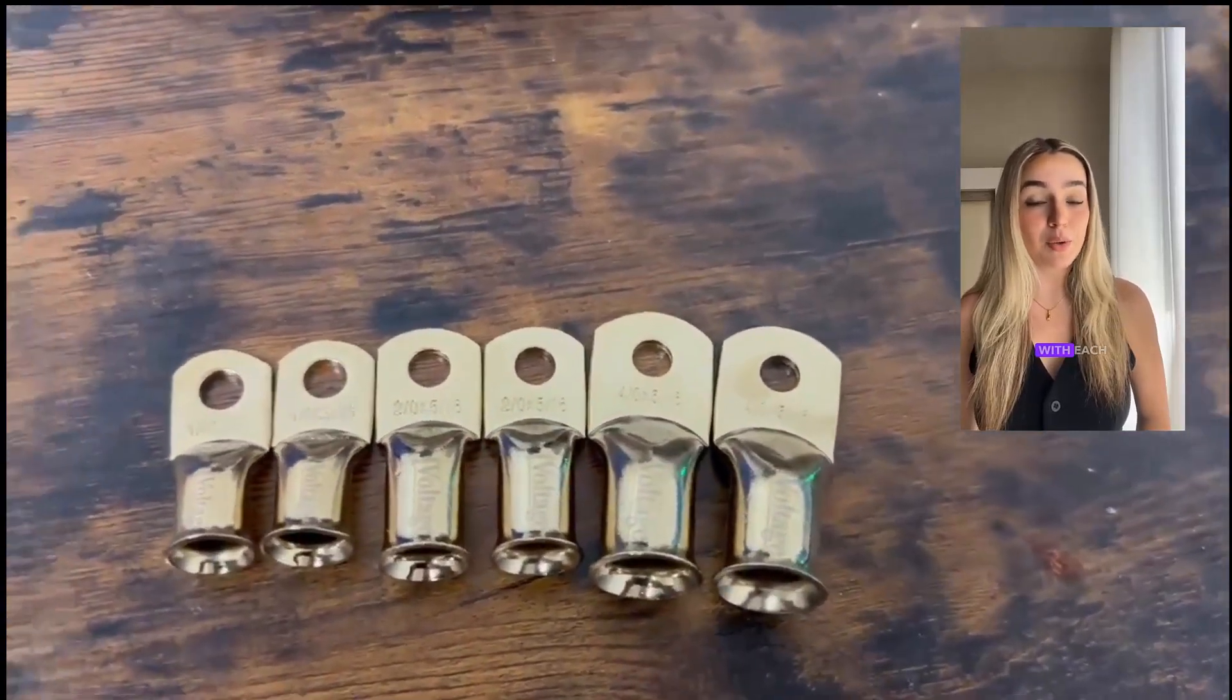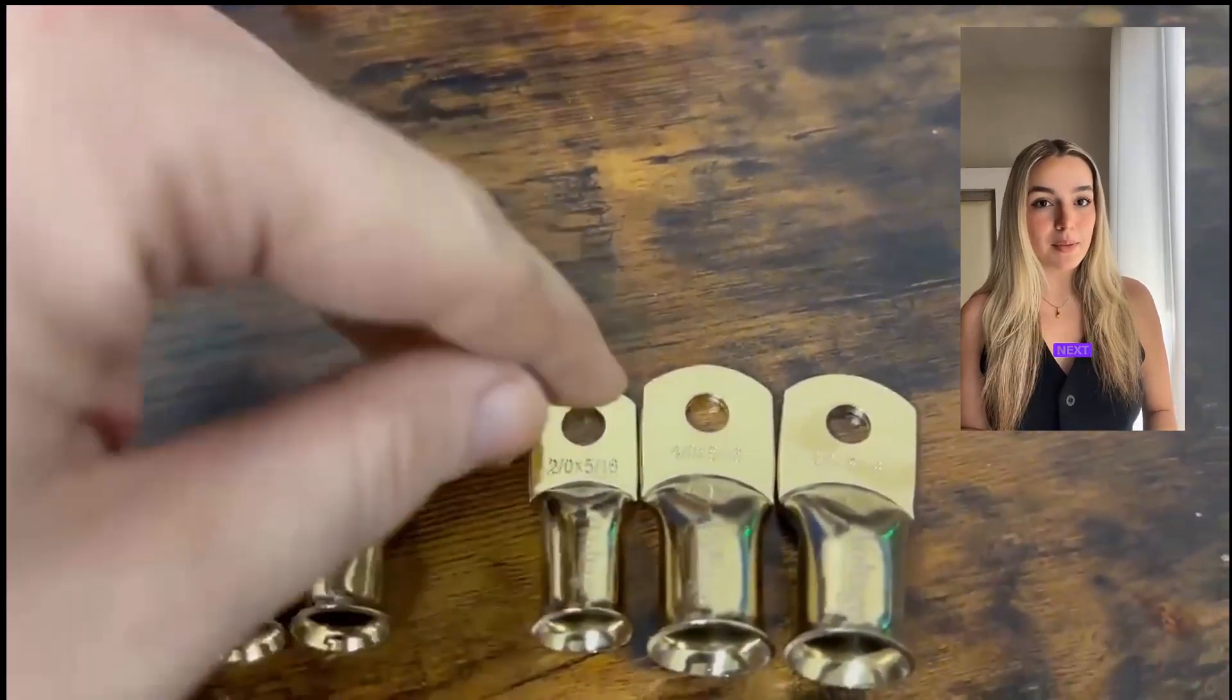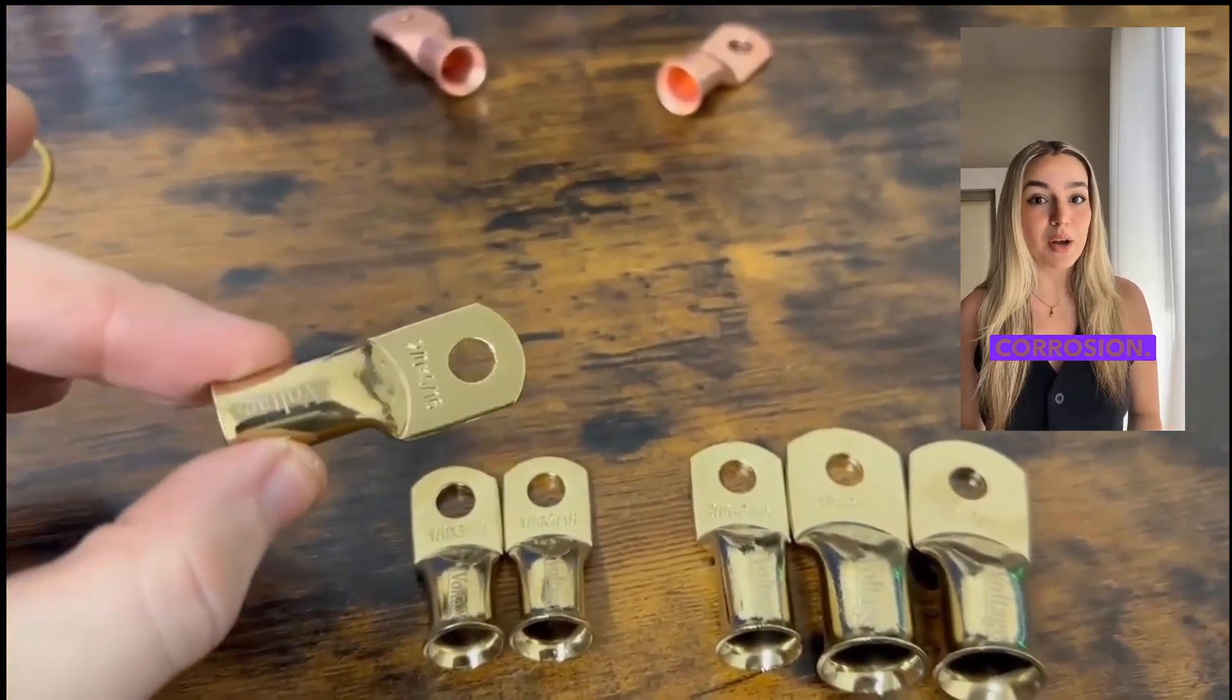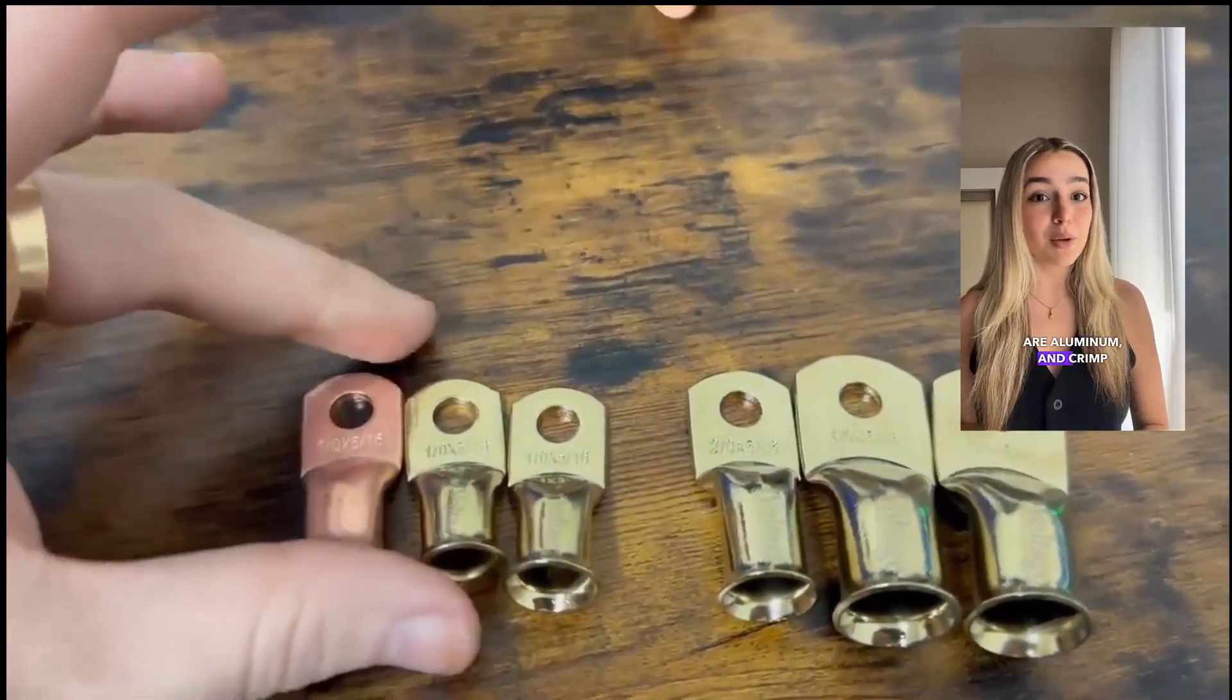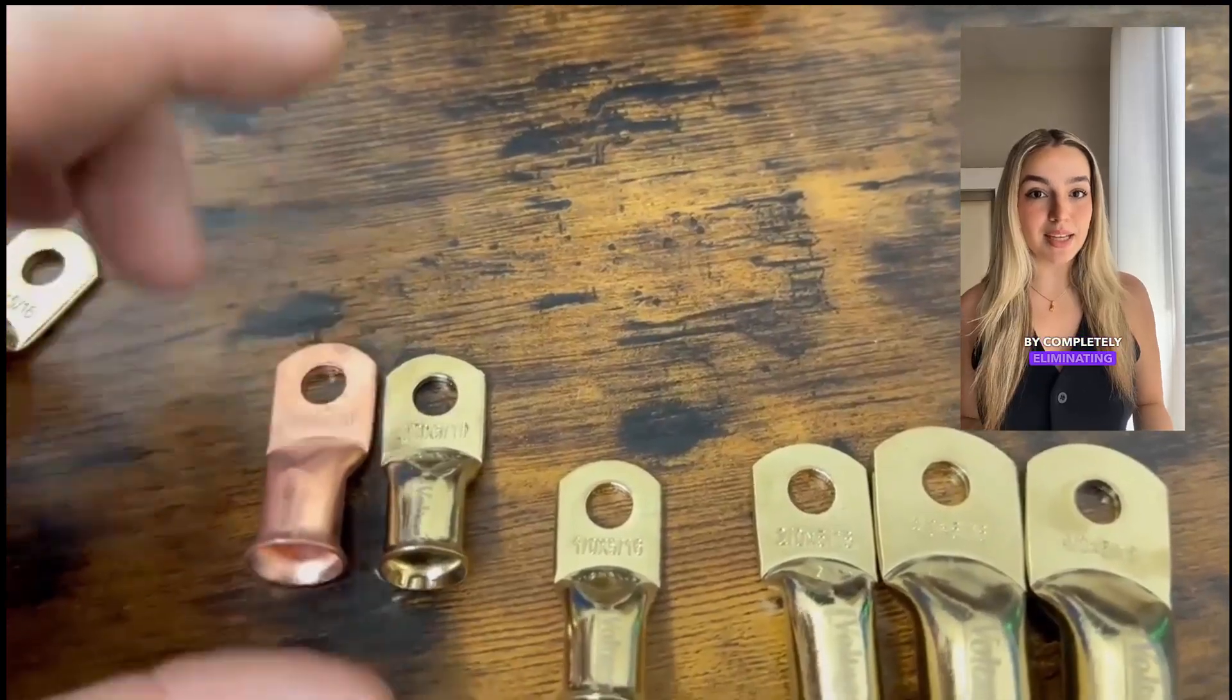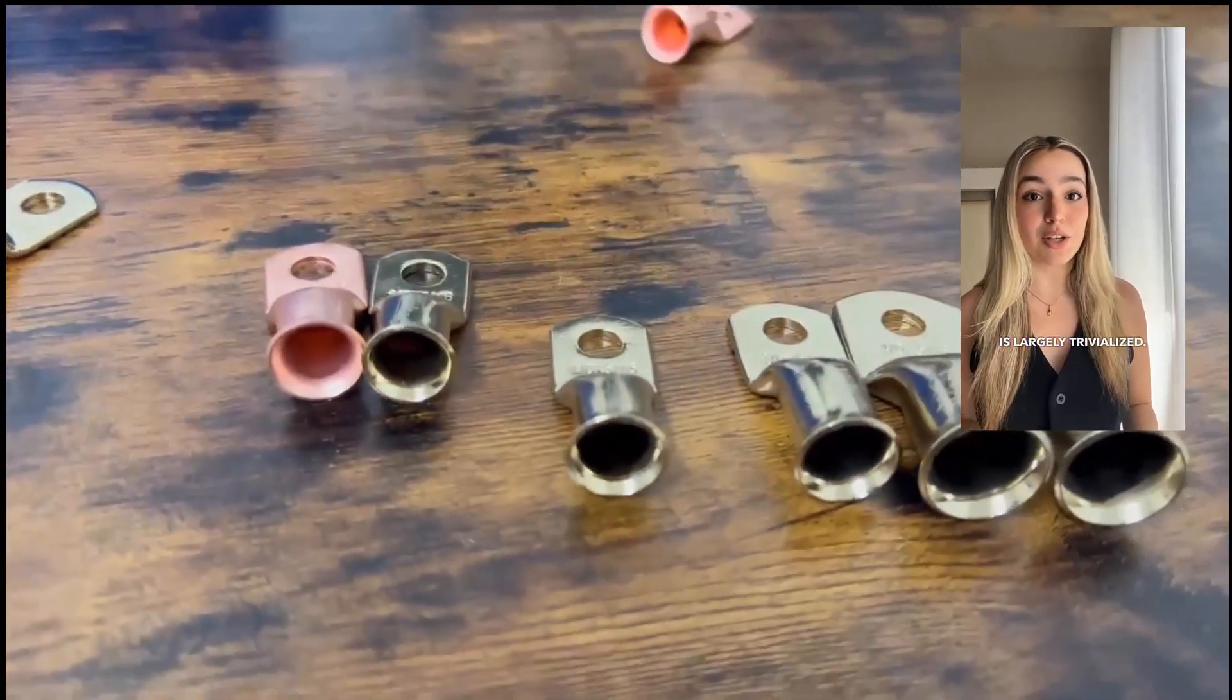Next benefit: highly reduced corrosion. Aluminum and copper connections are generally not recommended due to galvanic corrosion. Problem is, a lot of distribution blocks as well as battery terminals are aluminum, and crimp lugs are copper. This is why you will oftentimes see tinned copper lugs to help prevent this. By completely eliminating metal-to-metal contact with our lugs, galvanic corrosion is largely trivialized.